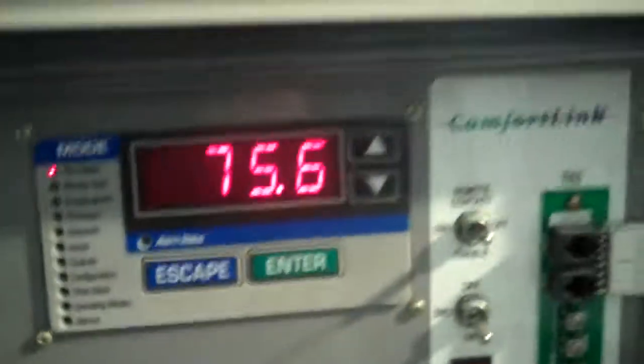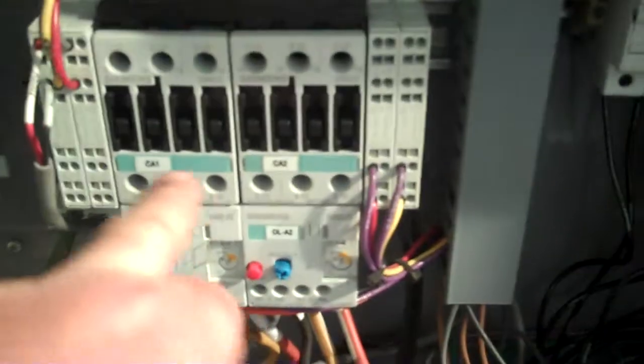We actually did install one new heater band on one of the 2 compressors. And before I forget, you can see that green color there. This is the refrigerant sight glass. It's a nice dry system. And then here's our Comfort Link controls and our various overloads and contactors for compressors, fan control, chilled water pump 1, chilled water pump 2, and the heaters I mentioned earlier. This does have the coil guard on the exterior, which is nice.